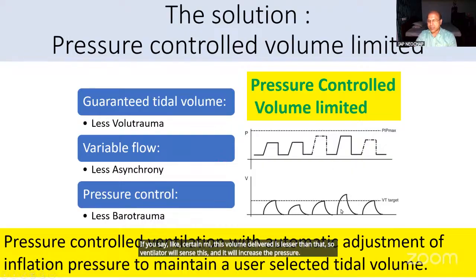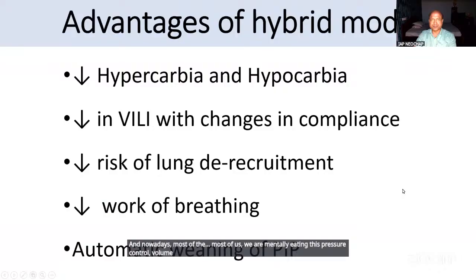I'll say other times the volume delivered is more. So say the 10 ml target was there, now it is delivering 15 ml. So the ventilator will sense this and it will decrease the PIP. So PIP will vary, but there will be a fixed maximum PIP. This is called pressure control volume limited ventilation. And nowadays, most of us are ventilating with pressure control volume limited ventilation.